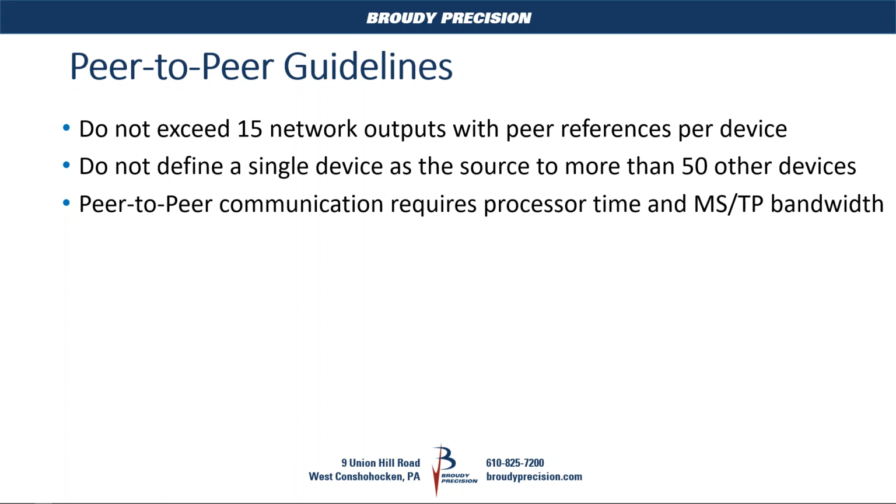And one thing you have to keep in mind is peer-to-peer communications does require processor time, and also it uses up MSTP bandwidth. So you've got all these communications going on between controllers on the network. So the more you have, the more bandwidth gets used up.